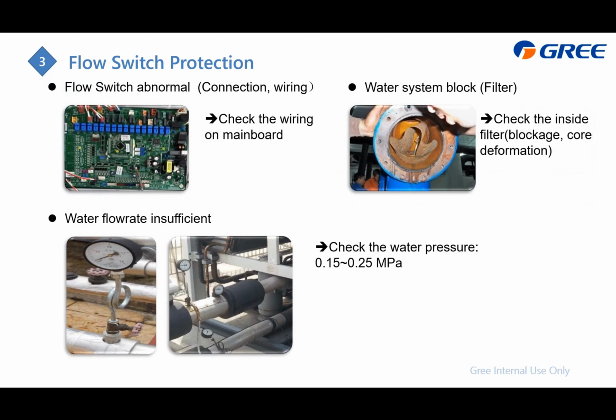Here are the details. For the flow switch, check the wiring and also the connection to the PCB. For the water system blockage, just focus on the filter, whether there is some blockage or core deformation, just like this. As for the water flow rate, if it is not enough, check the water pressure to ensure it is in this range.